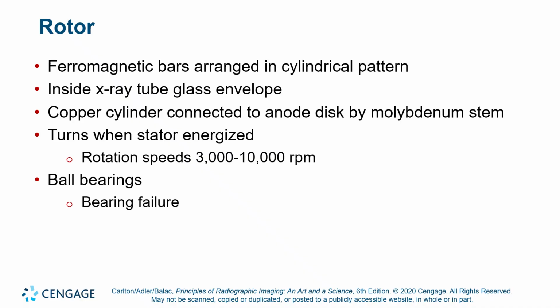Now, our rotor is supposed to rotate, but is also supposed to supply the positive polarity coming off of our rectifier and our high voltage transformer. And so it's got two important jobs: convey the positive charges to the anode target, but also develop a rotating magnetic field in response to the induction by the stator, and then start spinning. Typically we want RPMs between 3,000 and 10,000 RPMs to effectively spread the heat out.